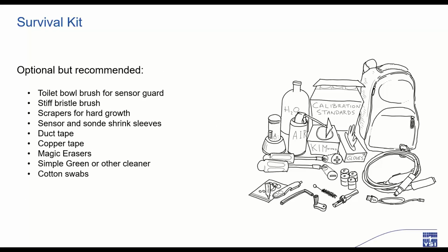Some of these other optional items are for removal and prevention of biofouling and may be helpful to keep in your kit as well. Of all the things on this list, my go-to for hard fouling is the putty knife or scraper. But I always have the other items just in case I need to clean up and reapply anti-fouling material prior to redeploying. If you take a small survival kit with you and a problem arises, you're going to be in a much better position to do some troubleshooting and hopefully get back on track and possibly avoid an unnecessary trip back to the site.